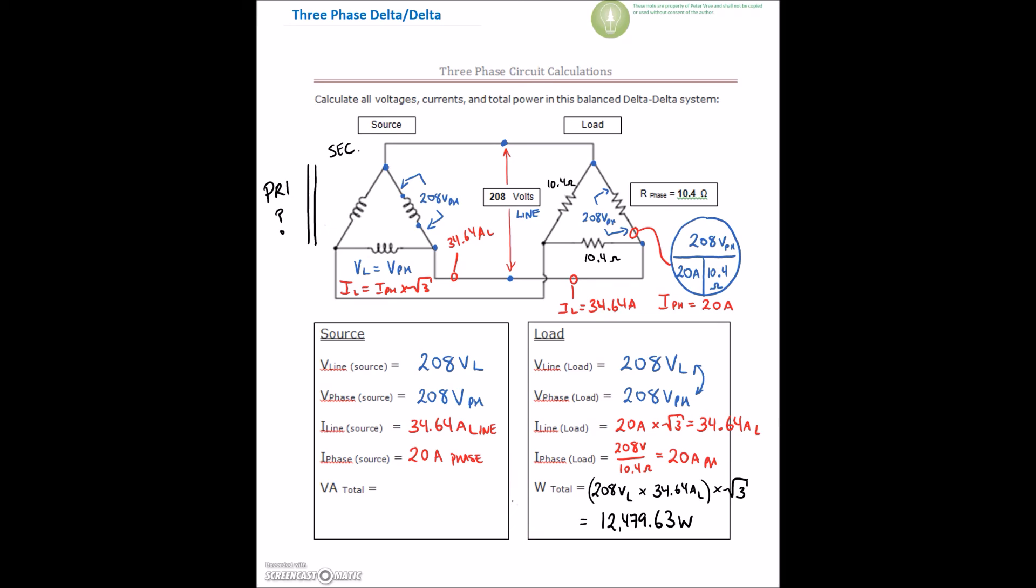So here we could also do our phase voltage, 208 volts on the phase, times our phase current. Our phase current was 20 amps. Multiply those guys by, not root 3. There's three phases, so I've got to multiply those guys by 3.